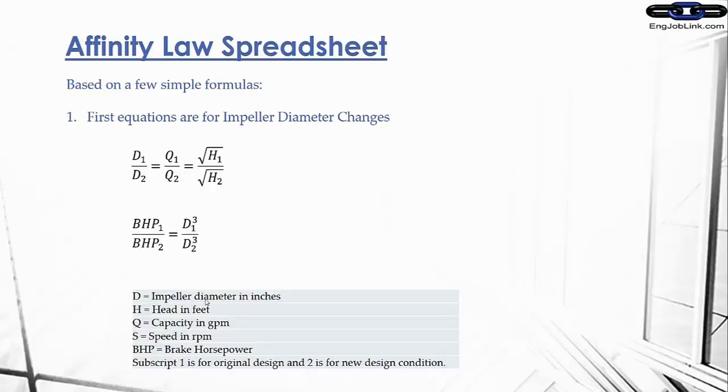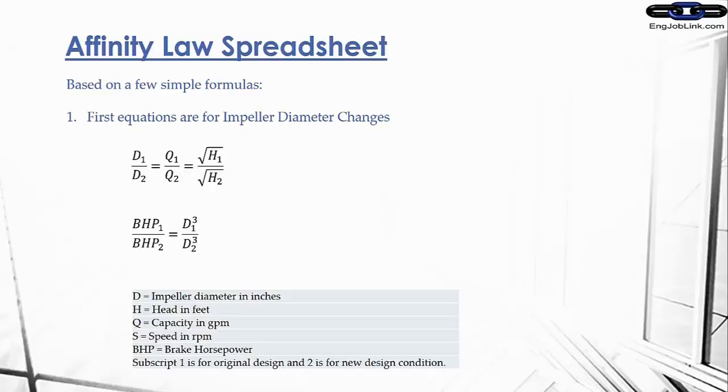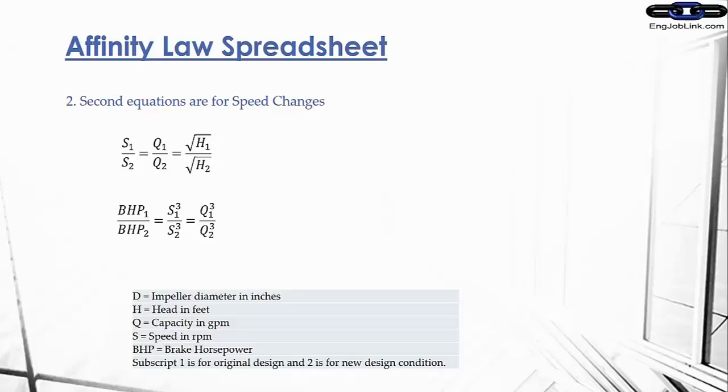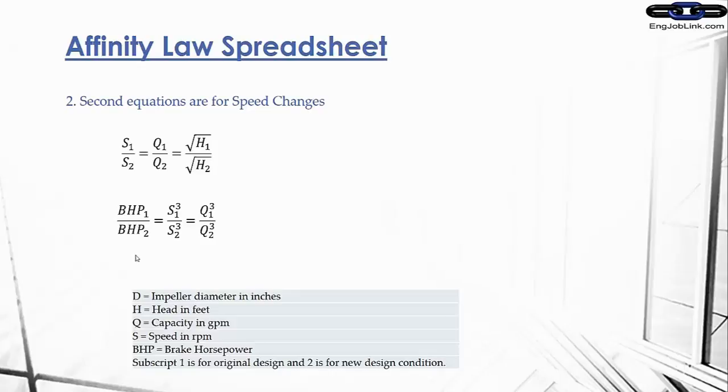In these equations, D stands for the impeller diameter, H is for head in feet, that's pressure, Q is capacity in gallons per minute, S is speed in RPM (revolutions per minute), BHP is brake horsepower, and you see subscripts 1 and 2. 1 is for the original design and 2 is for the new design condition. The second set of equations deal with speed. Speed is proportional to flow, same as before, and head is proportional to both of those to the square of both of those, and brake horsepower is proportional to the cube of speed and the cube of flow. So these are our basic formulas.